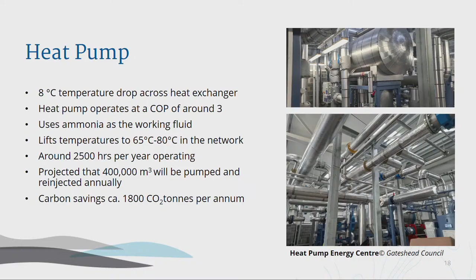It won't run continuously at 6 megawatts, so a lot of people think, if you're taking all this water out, how is it going to heat back up again? This scheme will probably run for about 2,500 hours a year. Eventually, it's going to ramp up over the next few years because some of the loads that will be connected are still being built. And we estimate that around 400,000 cubic meters will be circulated around that system annually. And they should have carbon savings of around 1,800 tonnes per year.